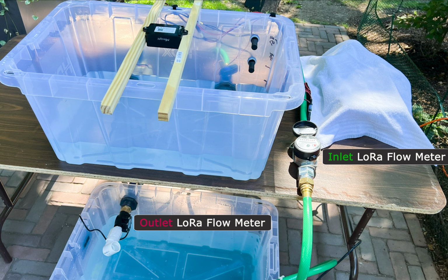Here are the 2 flow meters we are using on the prototype. The inlet flow meter is a commercial grade flow meter that outputs a pulse for every gallon of water. By counting the pulses, you can determine how much water entered the tank. The bottom flow meter is actually a smaller flow meter that can be used at tap stands as well as tanks, and it works just like the other flow meter. Both meters are hooked up to a LoRa sensor, which sends back flow data directed to the dashboard.